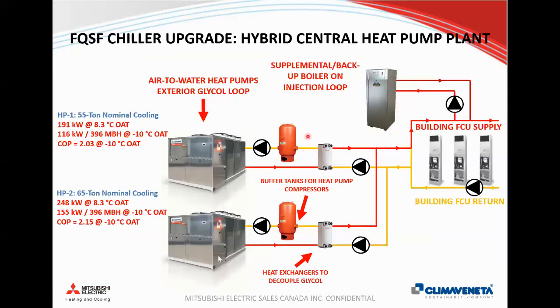So what's also different about this system is the way the boilers were put in and how the heat pumps were put in. So heat pumps, unlike a typical chiller, they're not drained in the wintertime. Heat pumps will need glycol in them, because if the heat pump's going to work down to -5, it could be in a thermal off state, so that water is exposed to, of course it's insulated, but that's not going to protect it from freezing. So you need glycol in the system. The second thing with heat pumps is you do need buffer tanks to prevent the compressors from short cycling.